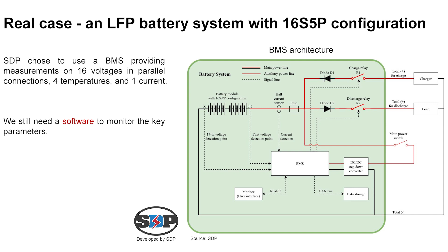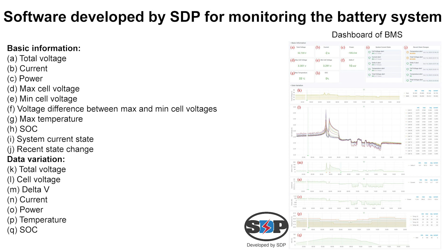Software for monitoring the battery system. Software for monitoring the battery system plays an important role in displaying the crucial data from the BMS. The remote dashboard of the BMS developed by SDP is shown in the figure. In the panel of basic information, some important physical and electric quantities, as well as the alert messages, are displayed, such as total voltage, current, power, max cell voltage, min cell voltage, the voltage difference between max and min cell voltages, max temperature, state of charge, SOC, system current state, and recent state change. Some data variations are also shown, such as total voltage, cell voltages, delta V, current, power, temperature, and SOC.